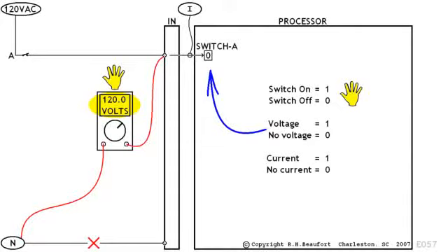It's fairly common practice for a technician to clip one of the voltmeter leads to a known neutral connection and then move the other probe from one point to another while looking for voltage. Quite a few technicians have been tricked by this setup. Their line of reasoning usually goes like this. Okay, I've got a good voltage signal coming into the module, so the switch and the wiring must be okay, but the bit still won't change to a 1, so the input module must be bad.